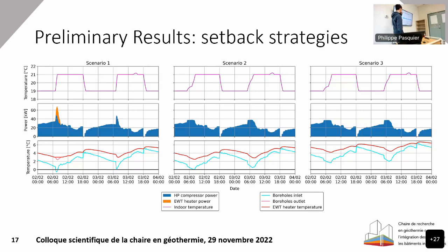And in the third scenario, you raise the bleed a little bit more, to 30%. What happens is that the water temperature doesn't go lower than about 1.6 degrees. And this is good because it keeps you in a safe position, let's say. Usually, when you require that much power, it is better to use the maximum bleed you can.